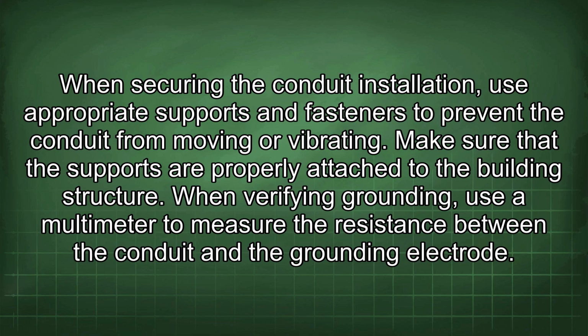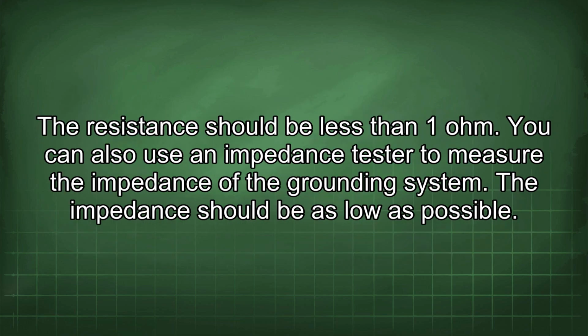When verifying grounding, use a multimeter to measure the resistance between the conduit and the grounding electrode. The resistance should be less than 1 ohm. You can also use an impedance tester to measure the impedance of the grounding system. The impedance should be as low as possible.